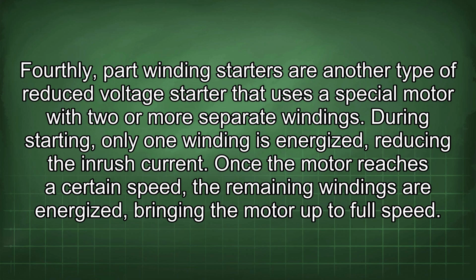Fourthly, part winding starters are another type of reduced voltage starter that uses a special motor with two or more separate windings. During starting, only one winding is energized, reducing the inrush current. Once the motor reaches a certain speed, the remaining windings are energized, bringing the motor up to full speed.